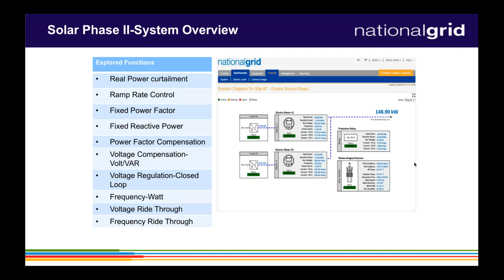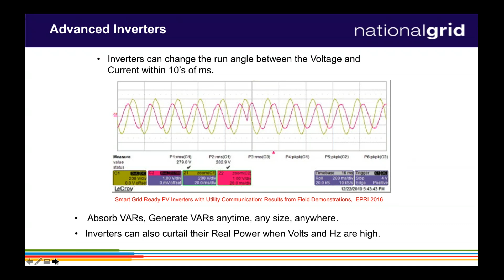Thinking a little bit more on lessons learned, inverters are really capable. This is a picture of a test where you can see this pink line is moving and an inverter is producing full reactive power. And within a cycle, it goes from lagging, absorbing, to leading. It's really impressive to think that that technology exists, that this inverter can do that on the fly. But understanding how that works with a larger system, the plant master controller, is really an important aspect.